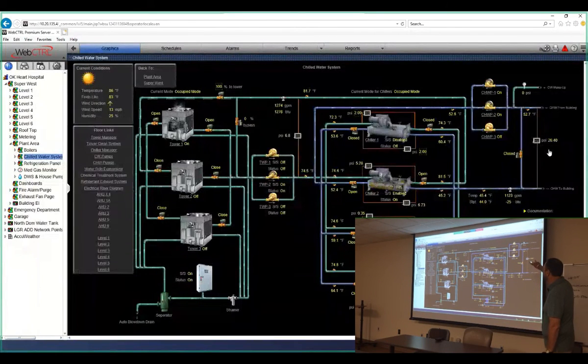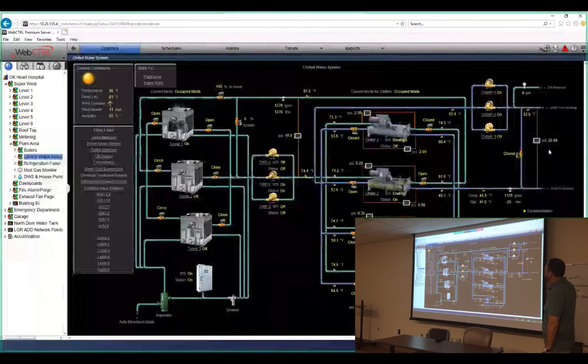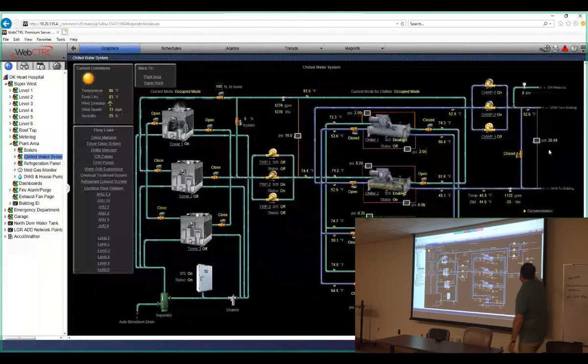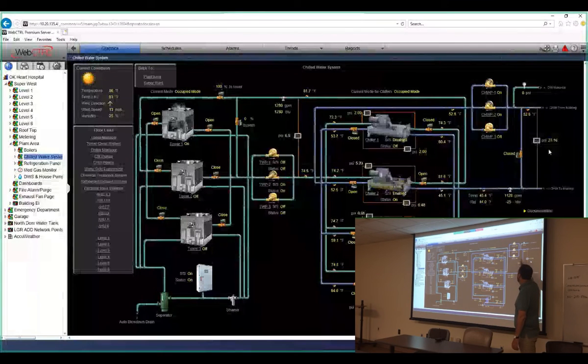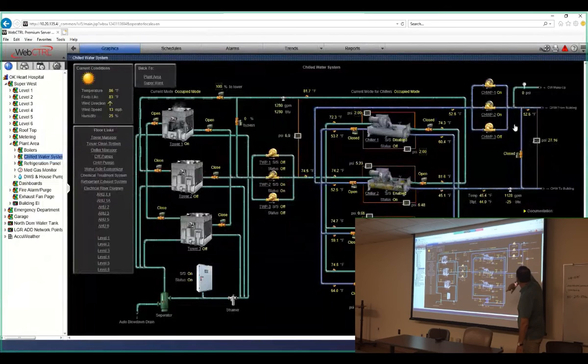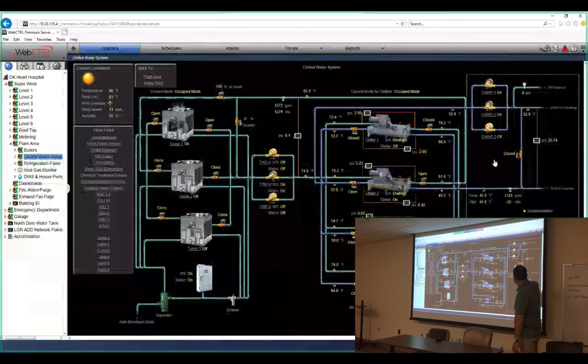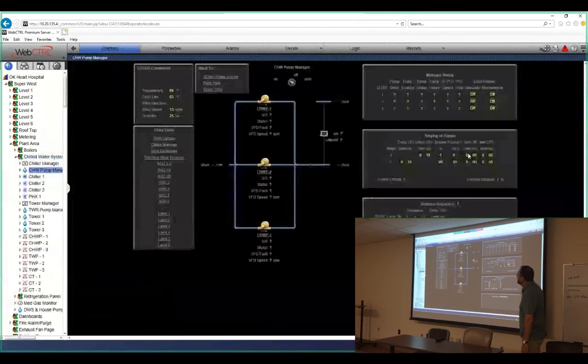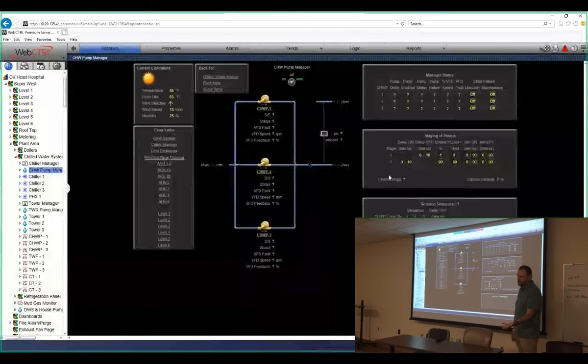The chill water pumps stage on to maintain that pressure. So if one pump can come on and stay running and maintain this pressure, then that's all you need. But if you need 2 pumps, the second pump comes on, and then they both ramp in sequence. You can click on that, probably over there, so go ahead and click right there. I think it'll take you to the... Right here? Anywhere over here, I think, will take you to the, yeah. See how it highlighted this? Should take you to the chill water pump manager.